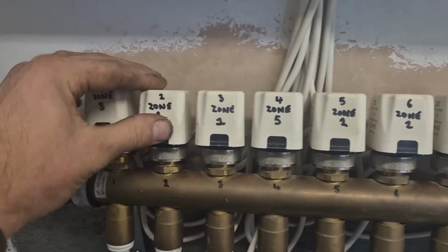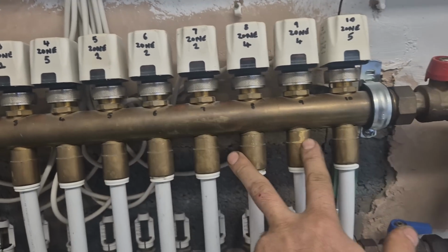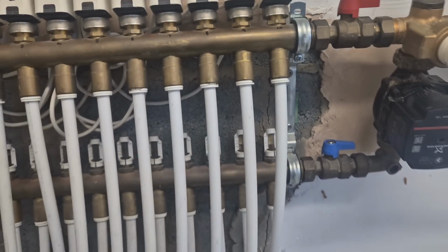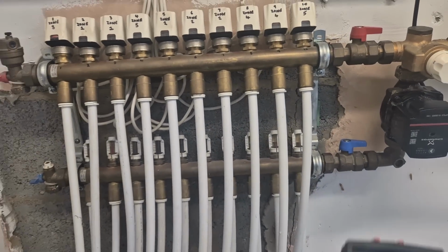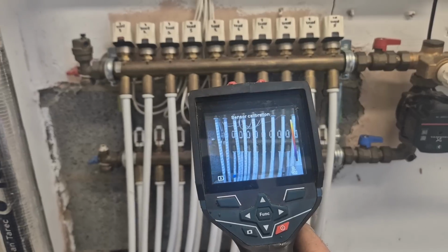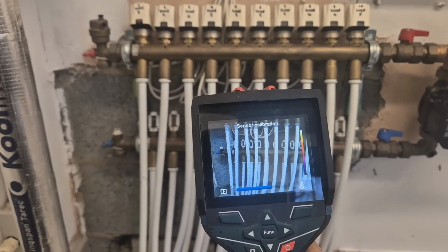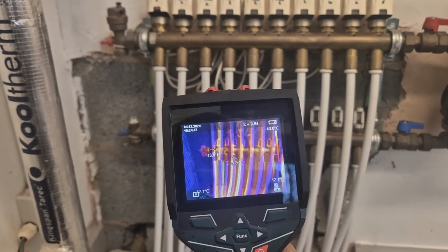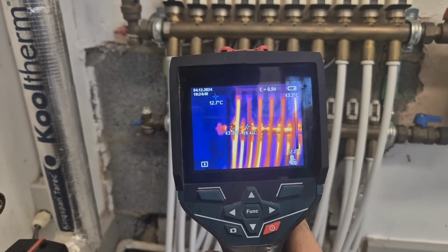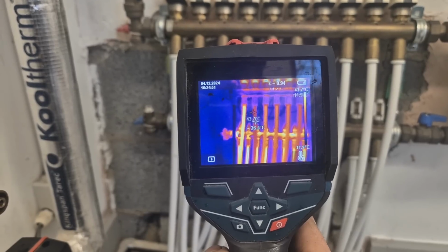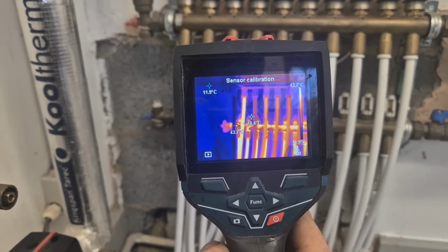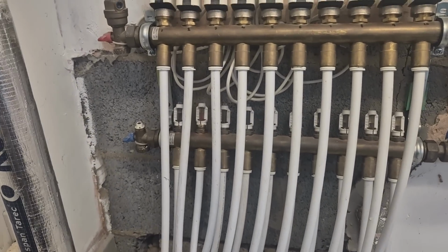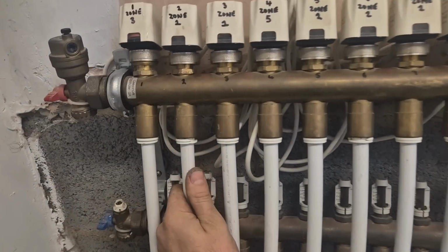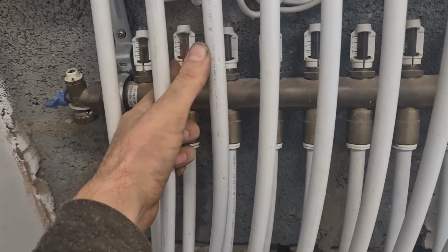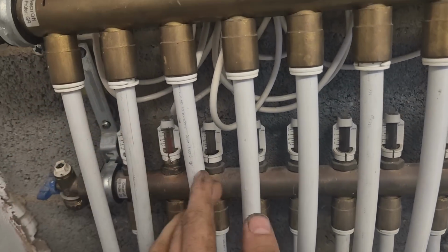I may have missed a stat, but these two, which one was it, zone 4, they should have water going through them now, which they didn't have before. But as I say, the original fault was just half of one loop that wasn't working, which I think was that one. It's still a bit cooler, isn't it? It's that second one from the left. The head's open on it, and it's just not letting as much through as the others.